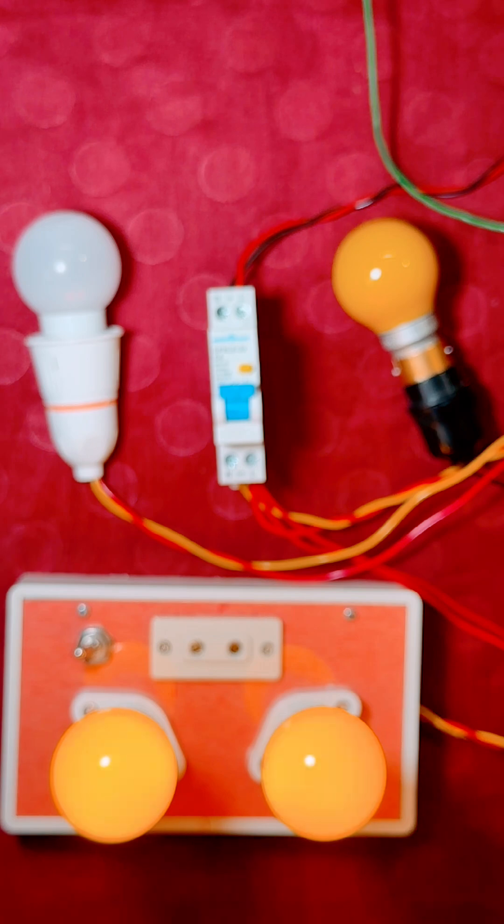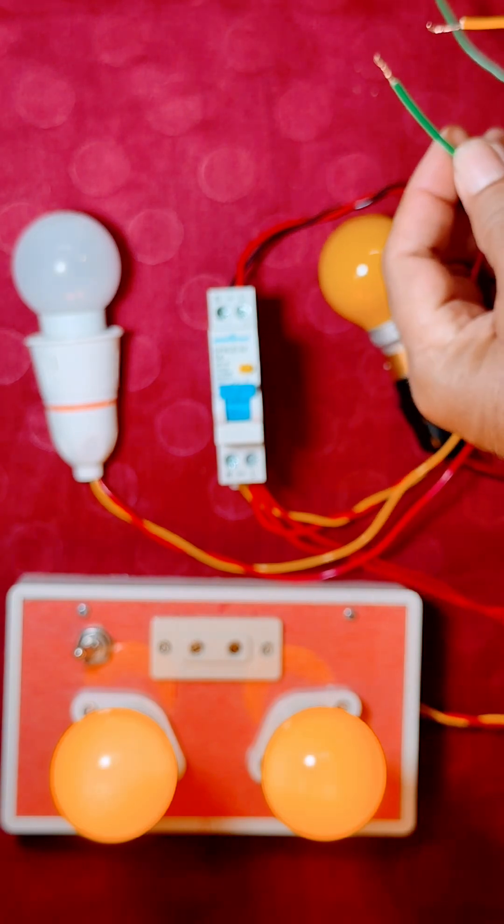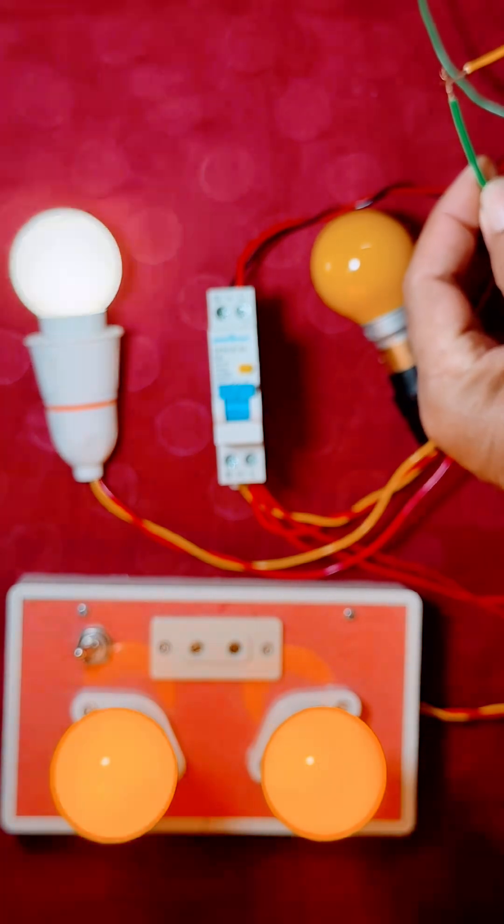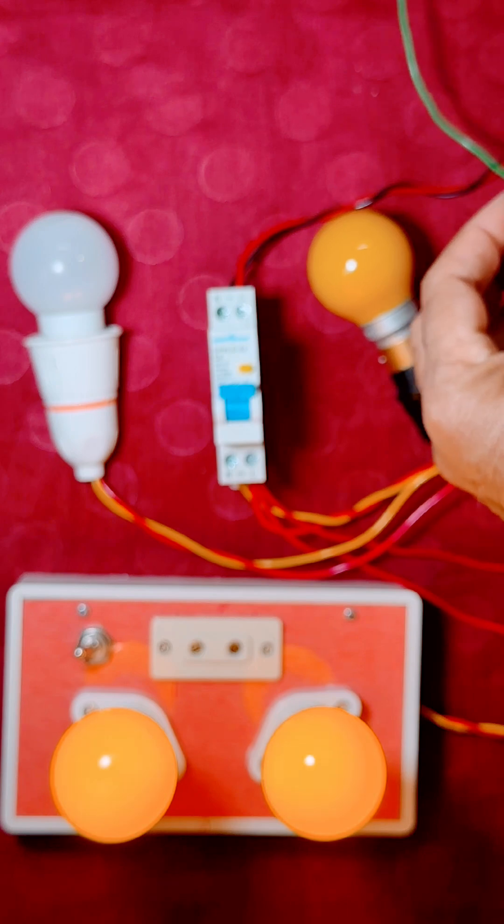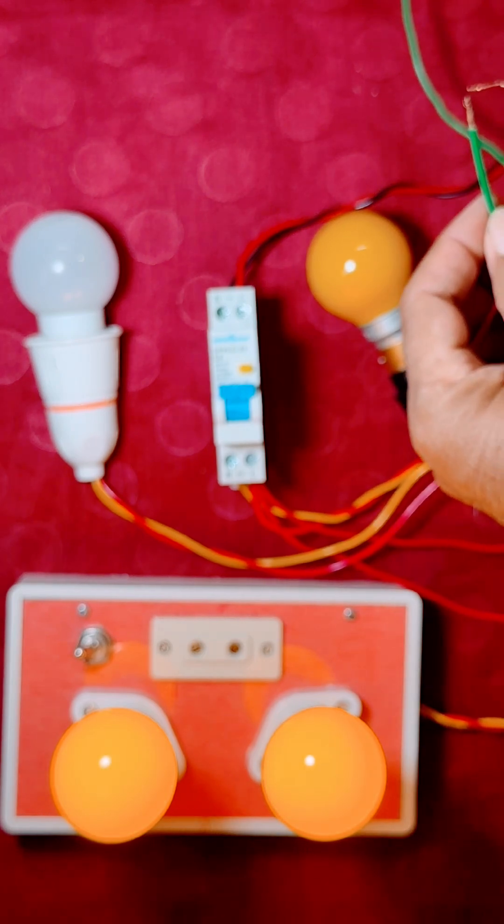Let's see. The yellow wire is conducting current to the earth wire. I connect it, it will glow, but the RCCB will not trip. But you have to see if the other wire is connected. That means if the yellow lamp is connected, it will immediately trip.